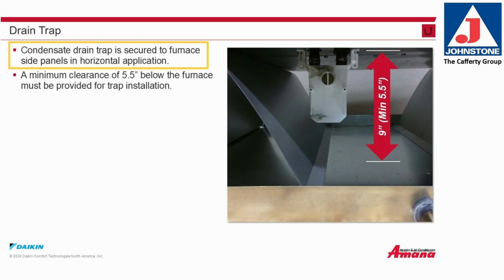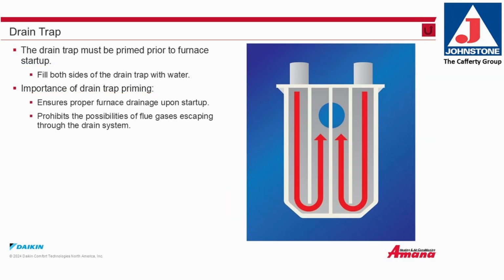Drain trap. The condensate drain trap is secured to the furnace side panels in horizontal applications. A minimum clearance of 5.5 inches below the furnace must be provided for trap installation. The drain trap must be primed prior to furnace startup. Fill both sides of the drain trap with water. The importance of drain trap priming is to ensure proper furnace drainage upon startup, and it prohibits the possibility of flue gases escaping through the drain system.